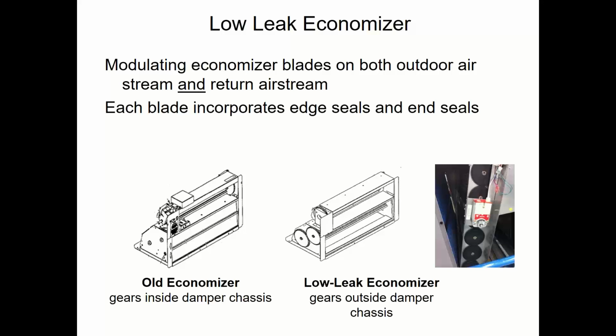So one of the 3 things that were done to make a damper low leakage are to move the gears from the inside to the outside, not the outside of the rooftop, just the outside of the airflow path, to put seals on the ends of the blades and on the edges of the blades. Those are the 3 things. Seals on the edges, seals on the ends, and then move the gears to the outside.